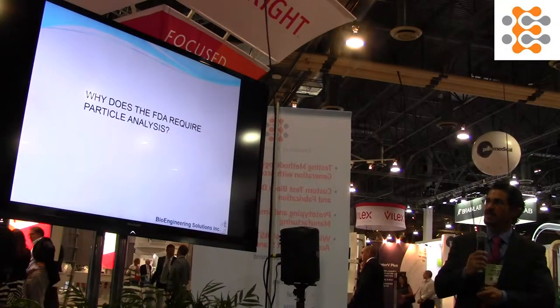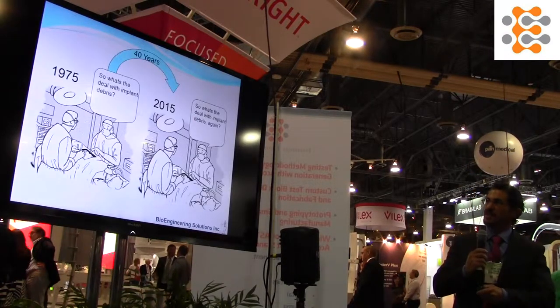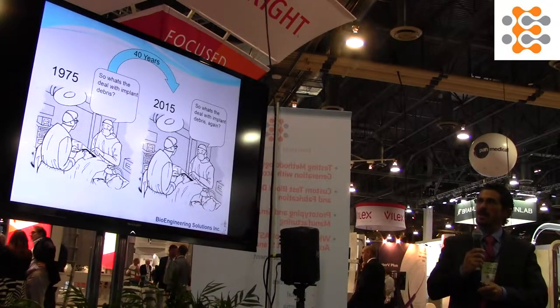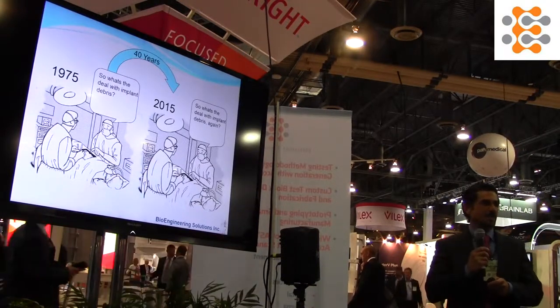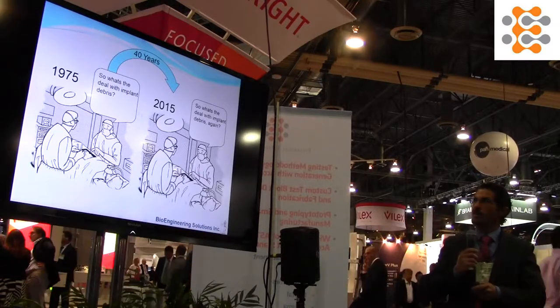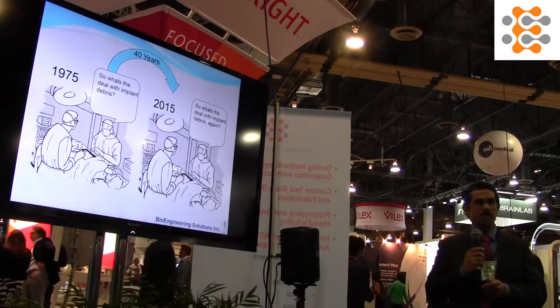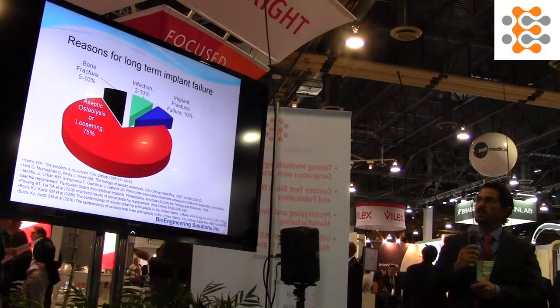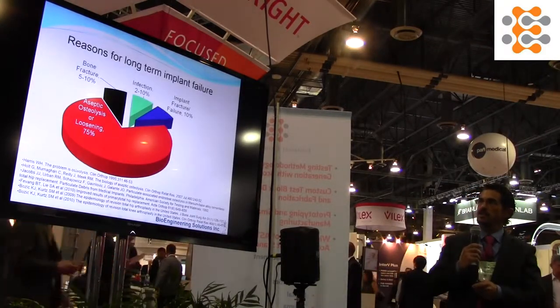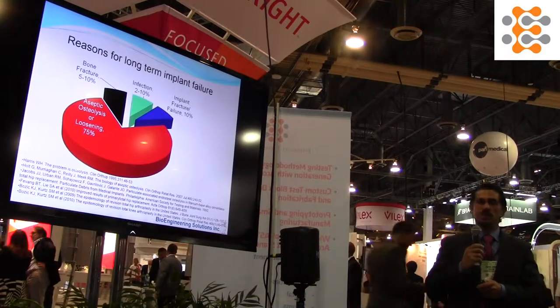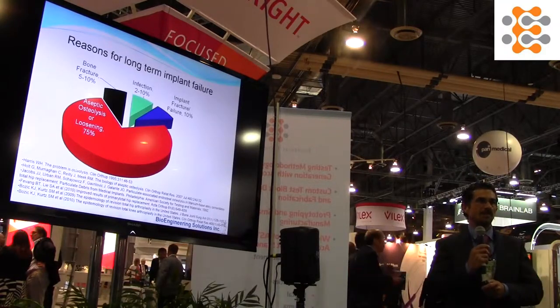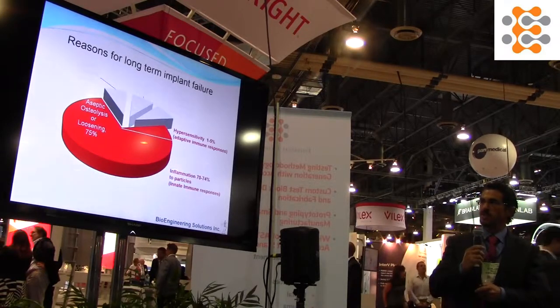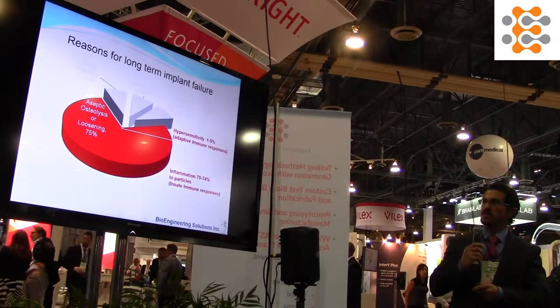Why does the FDA require particle analysis? Well, for the past 40 years, it's been fairly well recognized that implant debris is the reason for implant failure over time. Reasons for long-term failure include bone fracture, infection, and implant fracture, but the majority — 75% of it — is reaction to debris that is produced at the articulating surfaces.